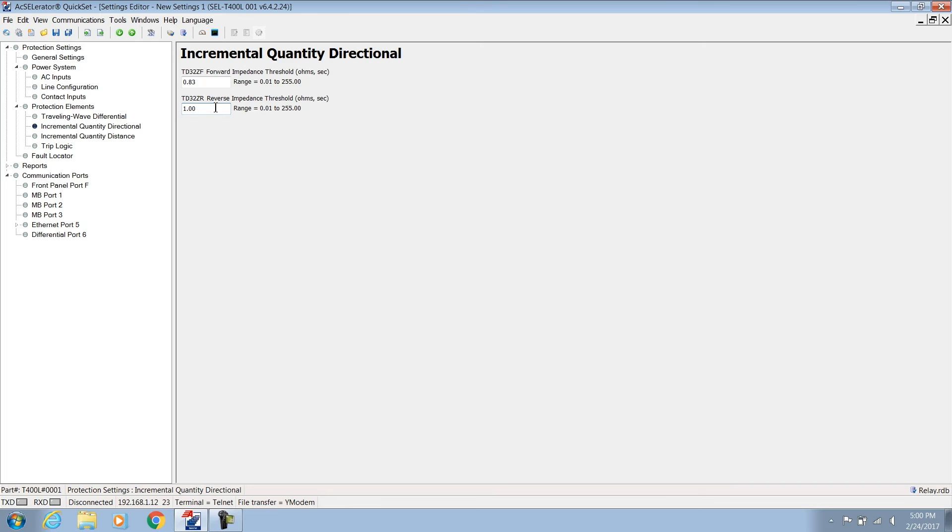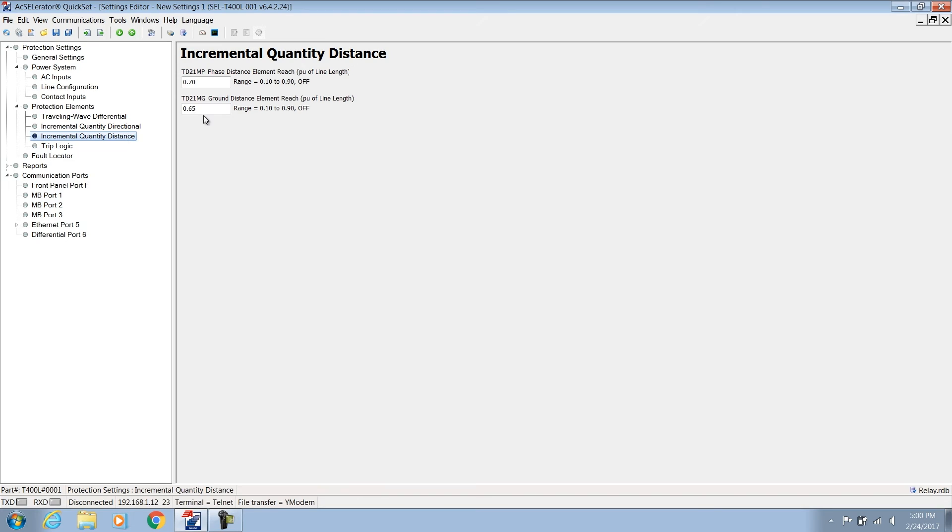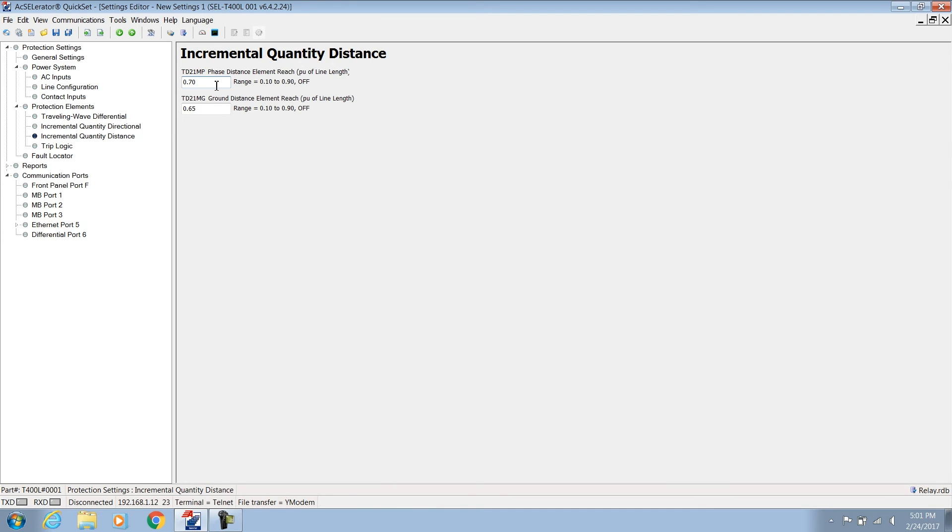A typical under-reaching distance element, that is a zone 1 that trips without communication, is set to about 70 or 80 percent of the line length. The SEL-T400L directly accepts the reach setting in per unit of the line length. The incremental quantity distance element, or TD21, has only two settings: the phase and the ground reach in per unit of the line. Let's assume the total error for the phase distance measurement is 15 percent including CT and PT ratio errors, line impedance inaccuracies, and the element's transient errors. Let's apply 5 percent of extra margin.